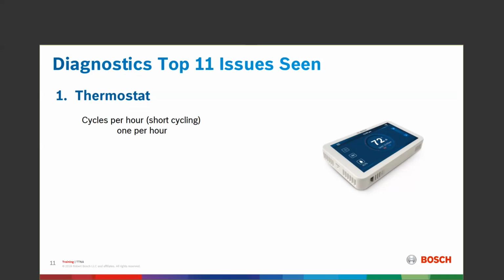That 3-second droop is enough for that compressor to shut down and start the sequence all over again. 3-minute delay, 3 minutes at 19 hertz, 3 minutes at 35 hertz. So that is basically 4 cycles per hour. We want to be aware of this in our thermostat so we don't have issues that point back to a heat pump that are really not heat pump issues.